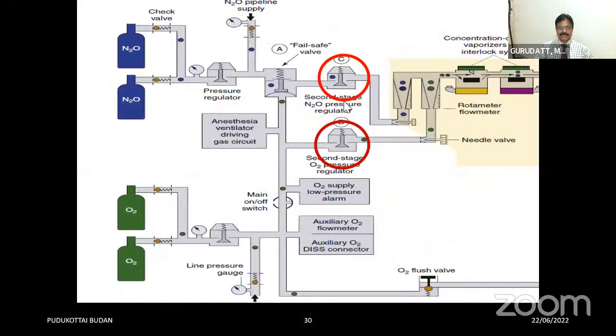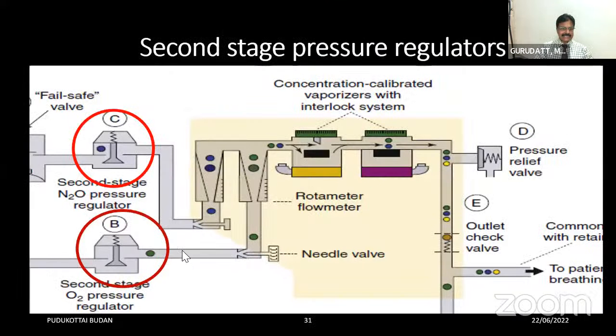Coming to the second stage pressure regulators, which are again components of the intermediate pressure system. These second stage pressure regulators are present only in GE machines. They are not there in the Draeger machines. In GE machines, these second stage pressure regulators are present just downstream of the failsafe valve and upstream of the flow control, the flow meter assembly. You can see here that the second stage pressure regulator further reduces the pressure of oxygen to 14 psig and the nitrous oxide outlet pressure to 26 psig.